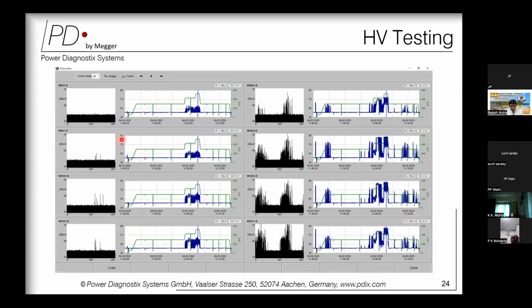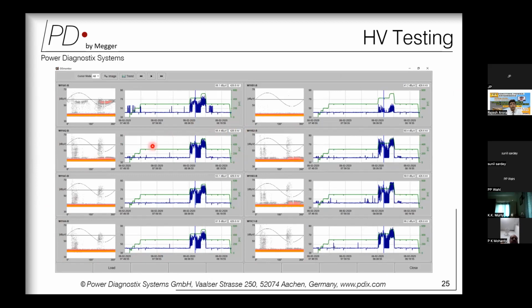So as we seen, you can record all channels parallelly. If a defect is being observed, we can switch the mode, and along with this recording, wherever there is a PD, we can also record the PRPD pattern. And when the PRPD pattern is recorded, the defect can be easily interpreted or easily known. So during this HV commissioning test, all this data are recorded parallelly: the instantaneous PD, the partial discharge inception voltage, extinction voltage, applied voltage, and the PRPD, and that becomes a fingerprint of your GIS which can be used in future.